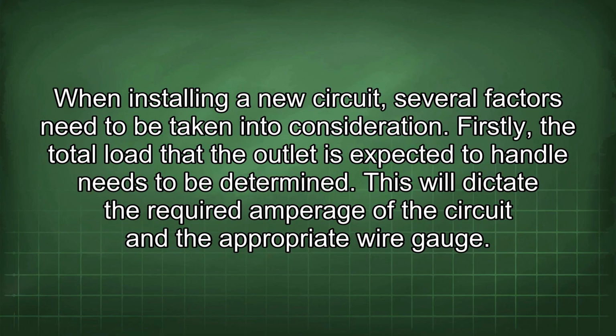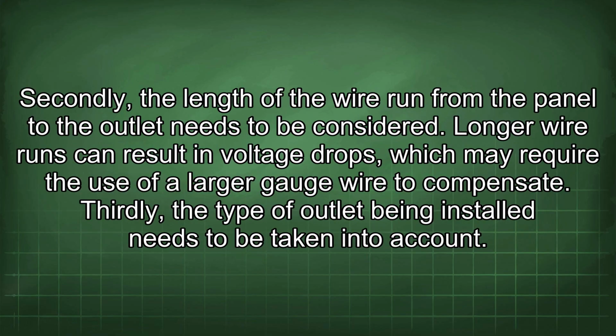When installing a new circuit, several factors need to be taken into consideration. Firstly, the total load that the outlet is expected to handle needs to be determined. This will dictate the required amperage of the circuit and the appropriate wire gauge. Secondly, the length of the wire run from the panel to the outlet needs to be considered. Longer wire runs can result in voltage drops, which may require the use of a larger gauge wire to compensate.